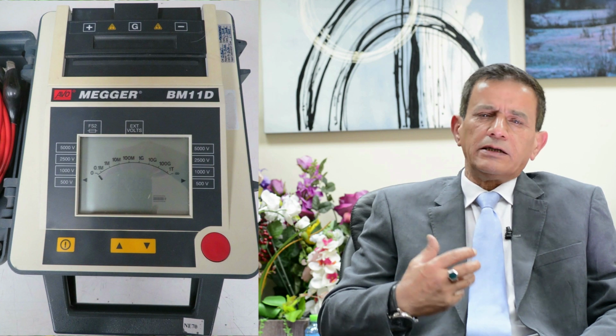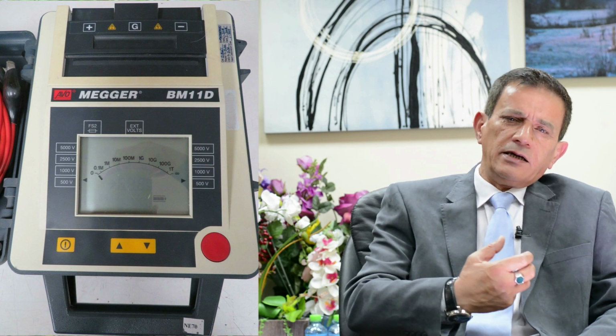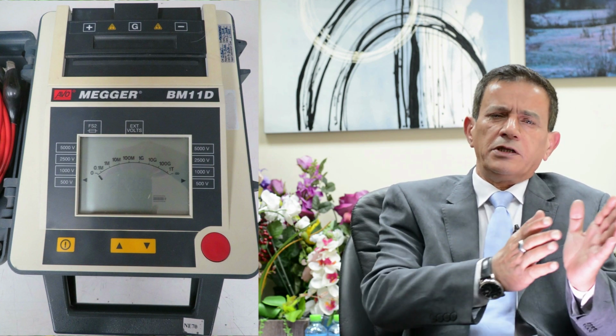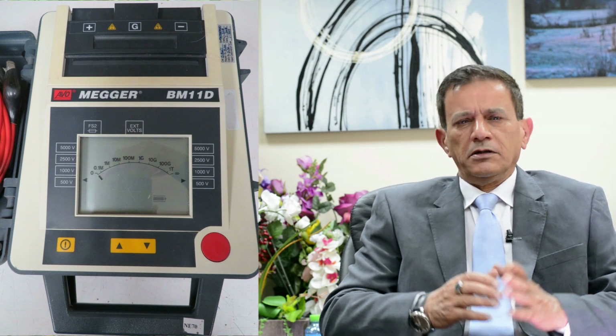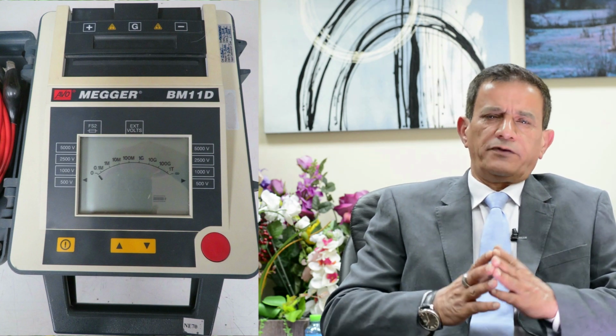Before we begin the test, we have to keep in mind that this insulation resistance is temperature dependent. Whenever the temperature goes up, the insulation resistance goes down, and vice versa. So we have to record the temperature while doing the test. The device used in this test is called the megger meter. The megger is the same as the ohm meter found in any multimeter, but the range is different.